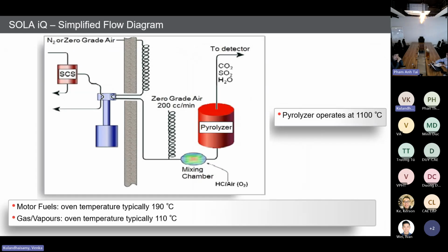Okay. Here, I have a simple flow diagram showing how the sample is injected into our oven, to the pyrolyzer. Over here, you can see the sample conditioning system. From the sample conditioning system, the sample is introduced to our injection valve. The injection valve will inject 1 microliter of sample. That 1 microliter sample is carried over by the carrier gas. Then finally, it will be injected into the mixing chamber. At the same time, zero grade air will come to the mixing chamber, so you will get thorough mixing here.